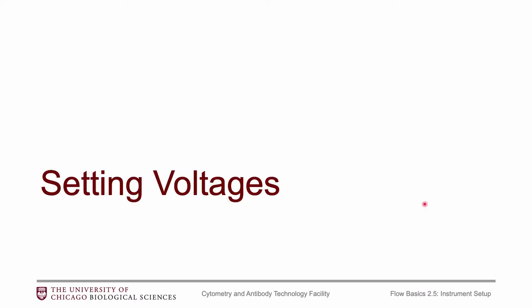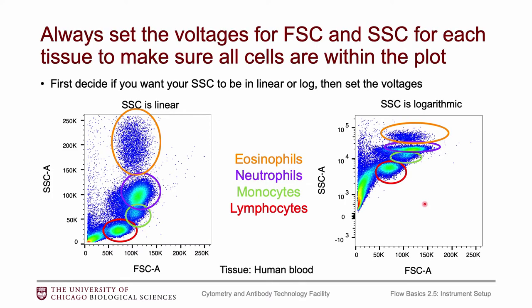Moving on to setting voltages. The first thing to decide is whether you want your side scatter in linear or log — it honestly doesn't matter, it's just a preference. Log is probably slightly more commonly used and is useful when you have a variety of cell types. For example, with eosinophils — which are very granular — and lymphocytes that are not granular, log ensures all cells are on the plot. In linear they get cut off a bit, but linear can be useful if you're using side scatter to actually separate populations, as you get a little better separation.